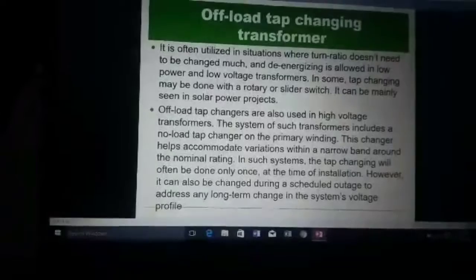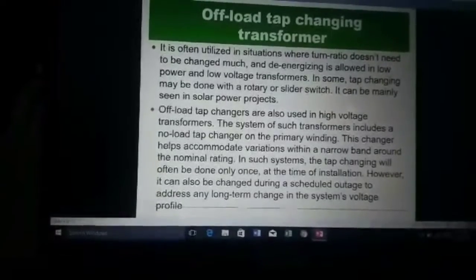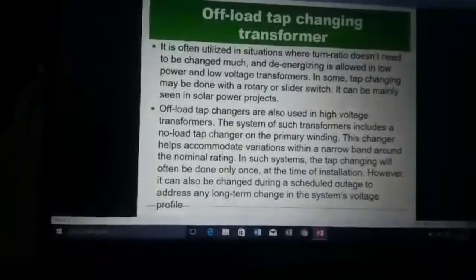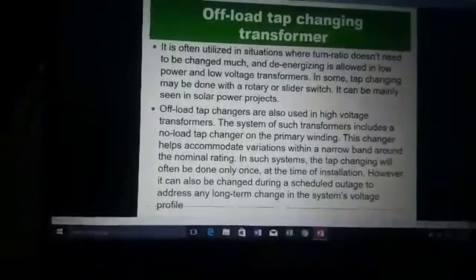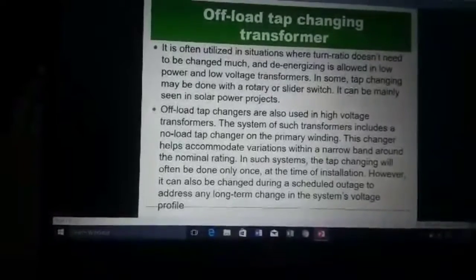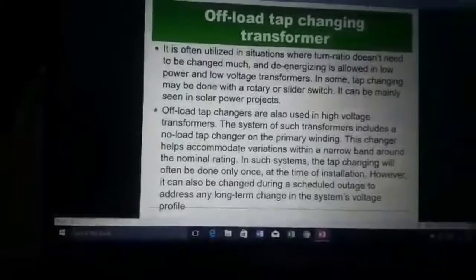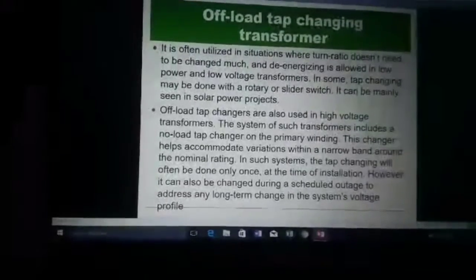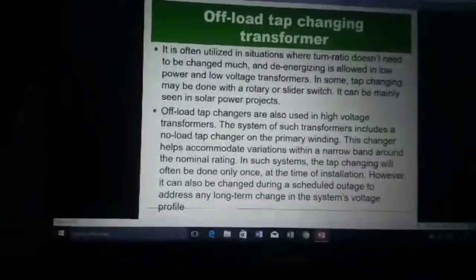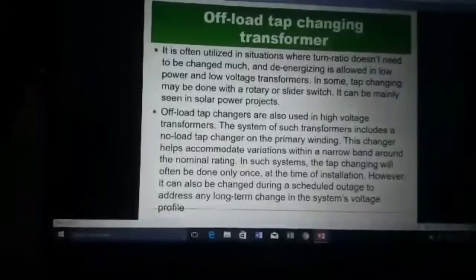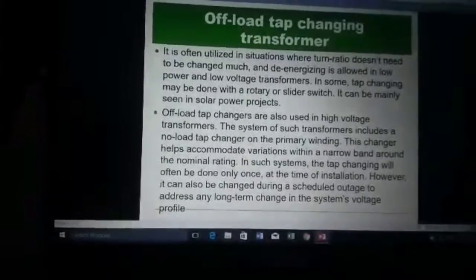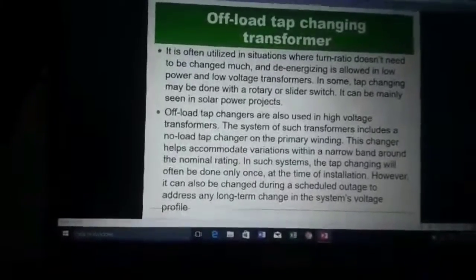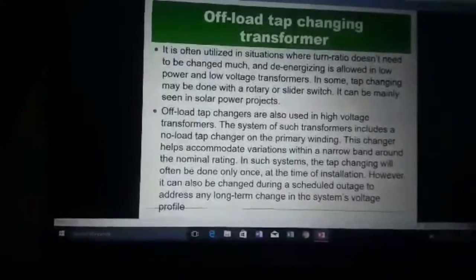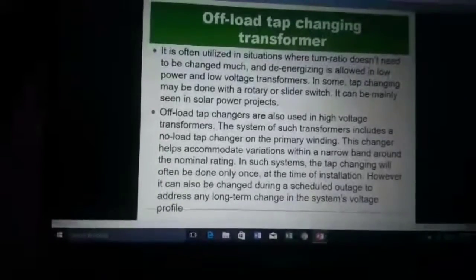The system of such transformers includes a no-load tap changer on the primary winding. This changer helps accommodate variation within a narrow band around the nominal rating. In such systems, the tap changing will often be done only once at the time of installation. However, it can also be changed during a scheduled outage to address any long-term change in the system voltage profile.